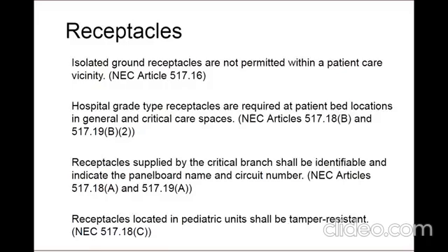Identification of critical branch supplied receptacles is very important to ensure medical equipment is connected to a reliable source. NEC 517.18(A) and 517.19(A) require the critical branch receptacles or the cover plate to be identifiable with a distinctive color marking, usually red, and also indicate the panel board and circuit number supplying them.